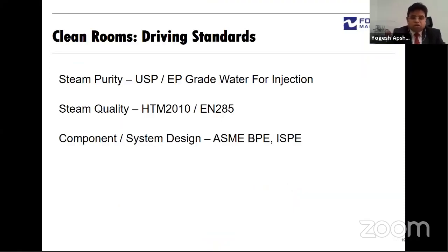Then coming down to the clean room, which are the driving standards. In the formulations, clean steam or pure steam applications comprise a very big amount of the steam user. Apart from the black steam or factory steam, we also have a pure steam or clean steam. There are different types of steam purity standards. One is the US Pharmacopoeia or the European Pharmacopoeia, which define the grade for water for injection. As far as the steam quality is concerned, we have the British standards, the Health Technical Memoranda, and the EN standard EN 285. And as far as the components and the steam system design are concerned, we have ASME BPE and ISPE, which is the International Society for Pharmaceutical Engineering.